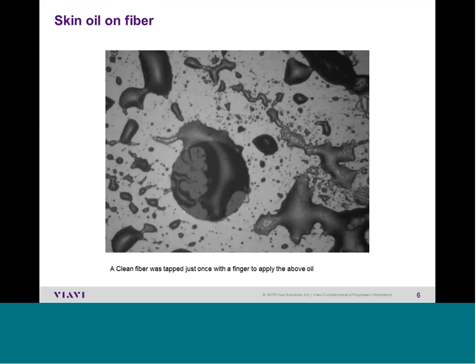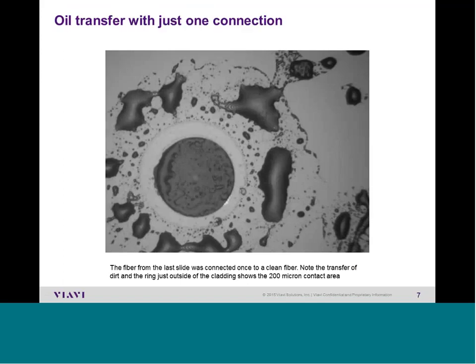If we touch the end of a jumper with the inside of our hand for just a tiny amount of time, almost all of us will apply a generous helping of skin oil onto the clean fiber. Take this now-contaminated fiber and plug it into another one, and the perfectly clean fiber becomes filthy with oil. Notice there is a ring on the fiber — here is the 125-micron cladding, and out at 200 microns we see a ring.